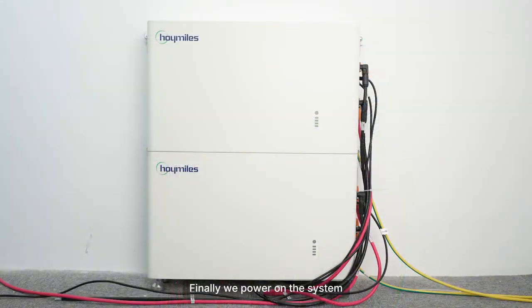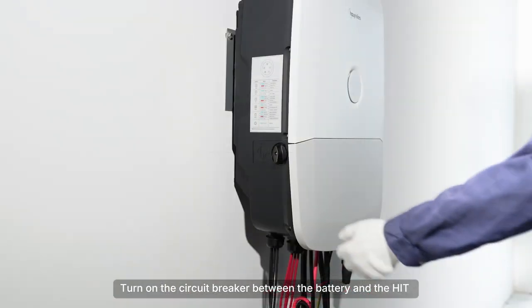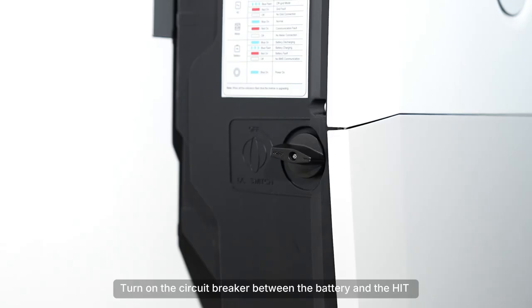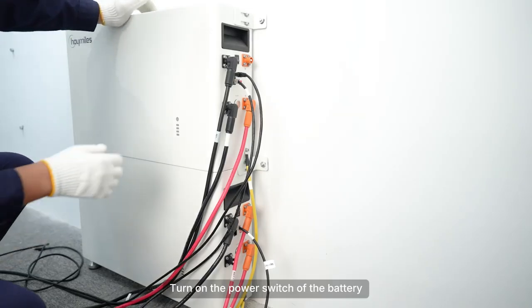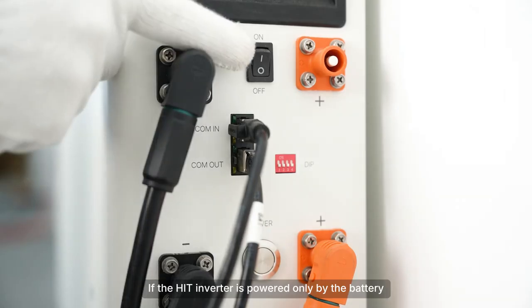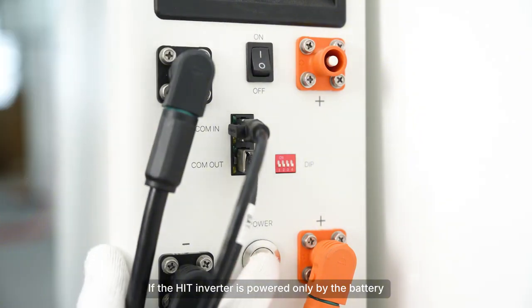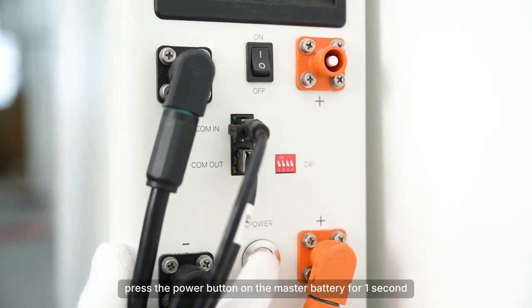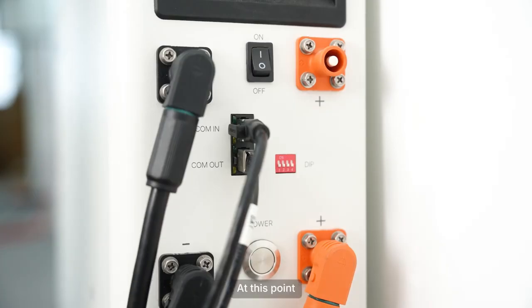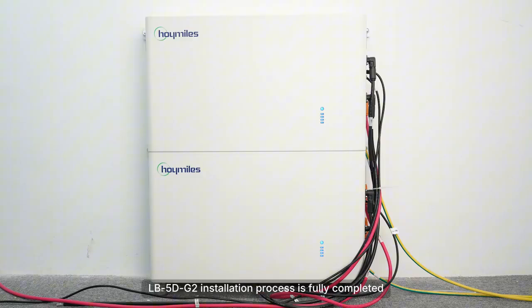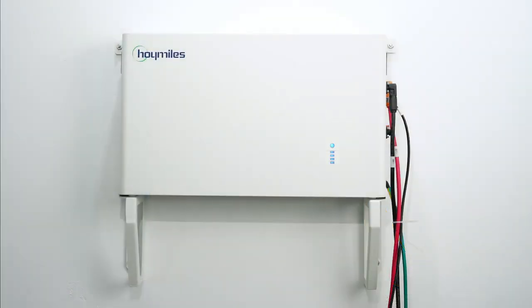Finally, we power on the system. Turn on the circuit breaker between the battery and the HIT. Turn on the power switch of the battery. If the HIT inverter is powered only by the battery, press the power button on the master battery for 1 second. At this point, LB-5D-G2 installation process is fully completed.